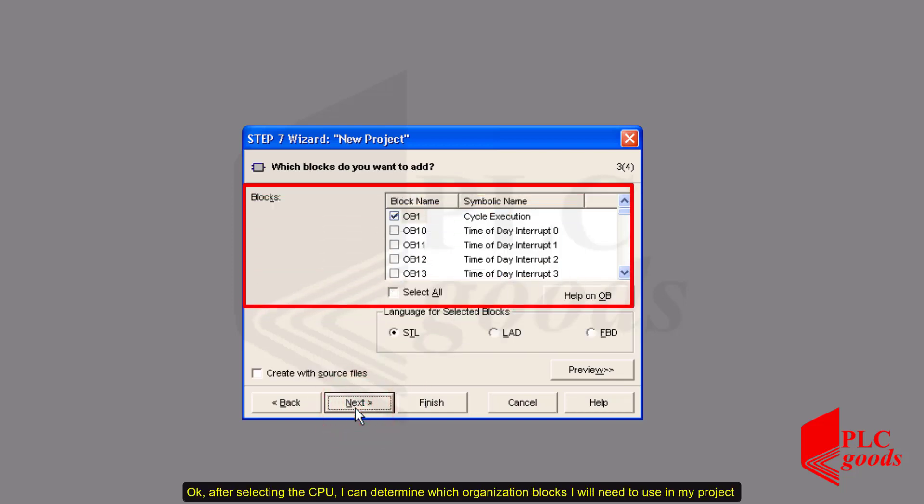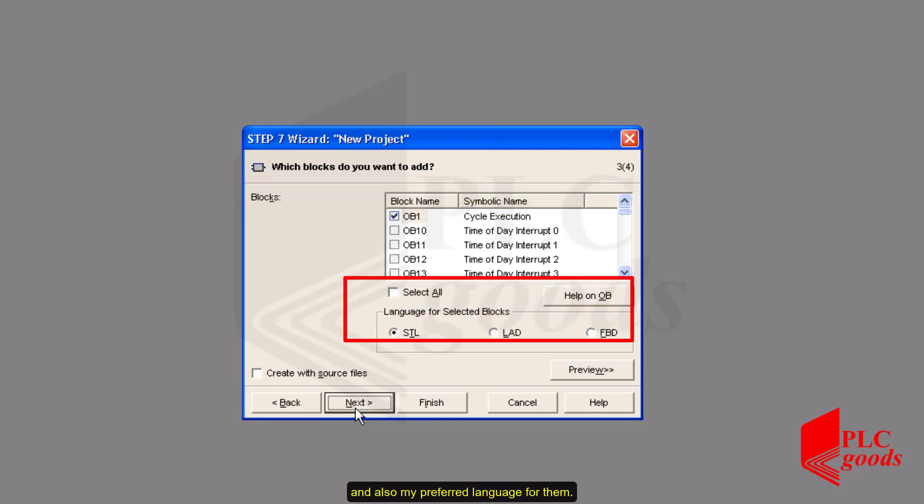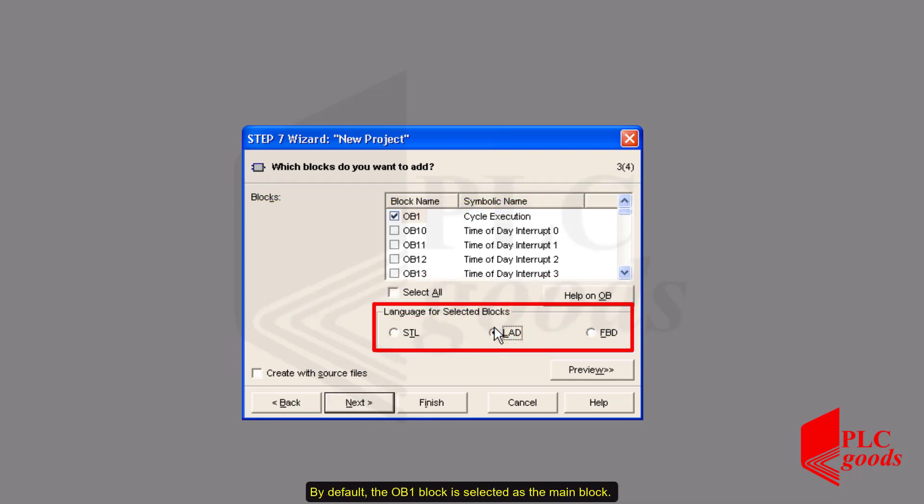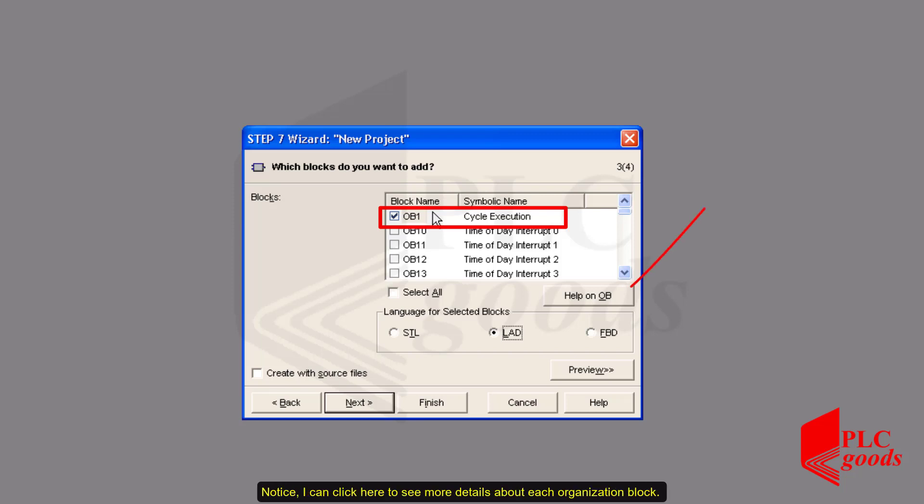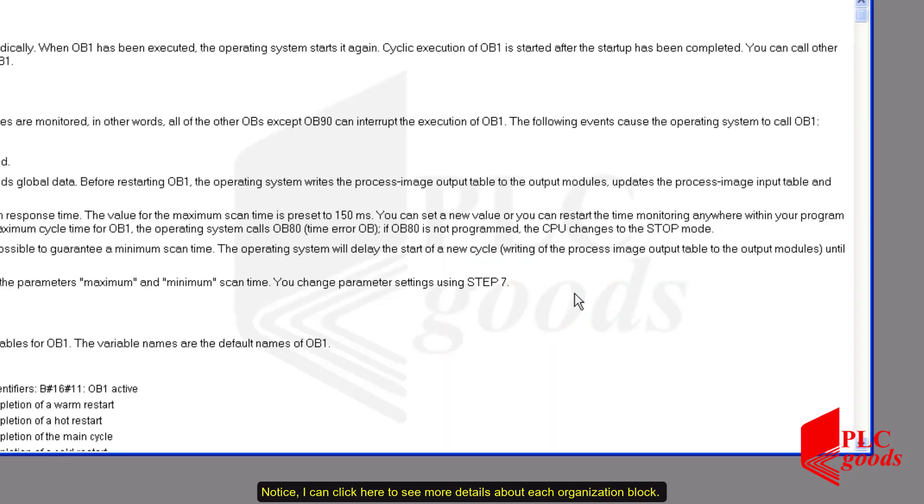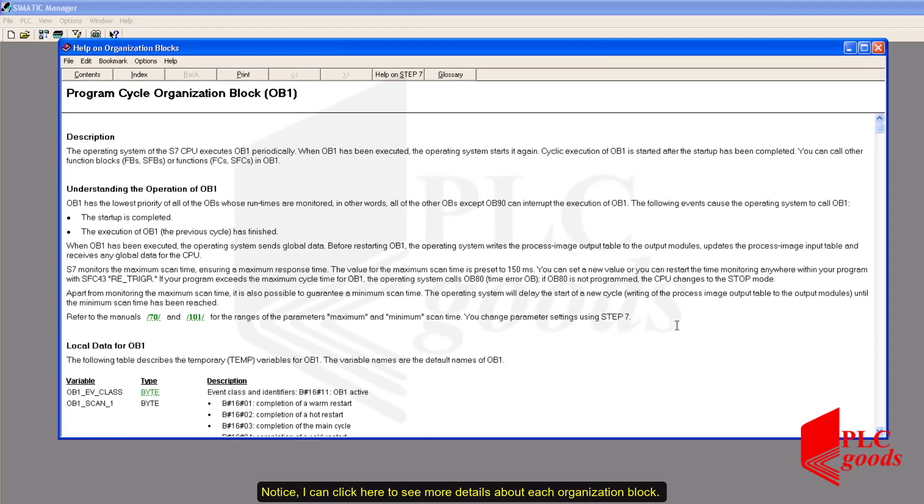After selecting the CPU, I can determine which organization blocks I will need to use in my project and also my programming language for them. By default, the OB1 block is selected as the main block. It's executed cyclically when the PLC is in the running mode.